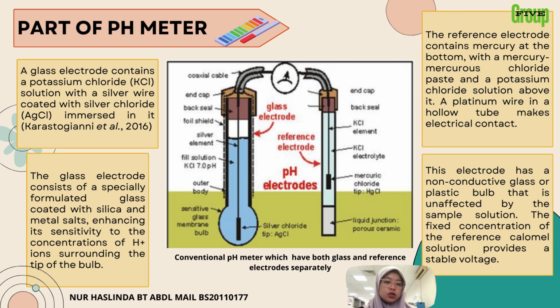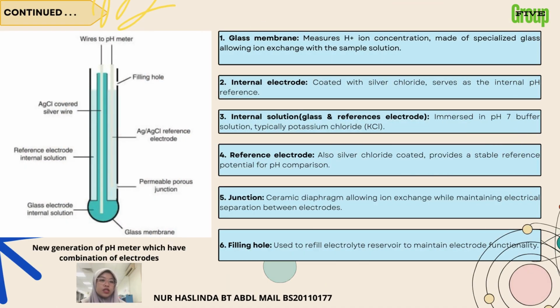This reference electrode is housed in a non-conductive glass or plastic body that is not affected by the sample solution. The reference solution within it maintains a fixed concentration, providing a stable voltage necessary for accurate pH measurement. Now, let's talk about the new generation of pH meters, which use a combination electrode.